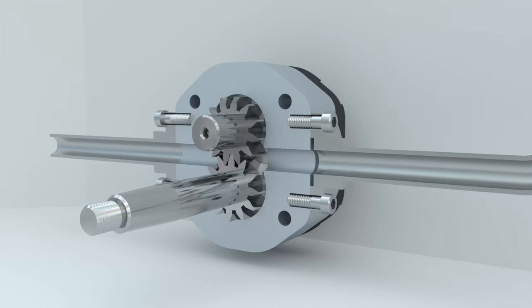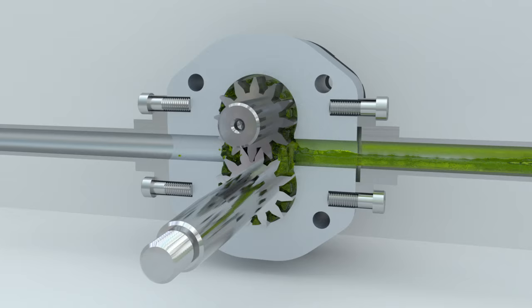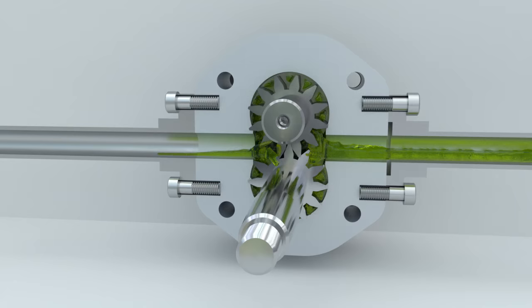When the gear teeth come out of the mesh, the volume of the chamber increases and the pressure inside becomes lower than atmospheric pressure. Fluid from the tank enters the pump and fills the space between the gear teeth and the housing.